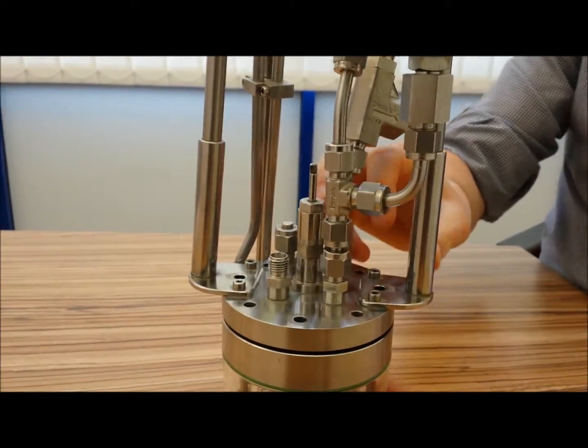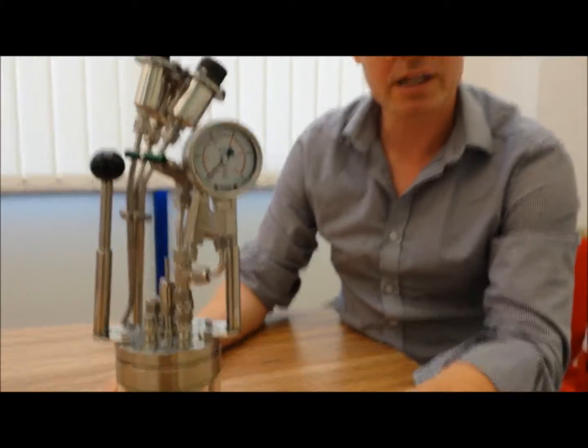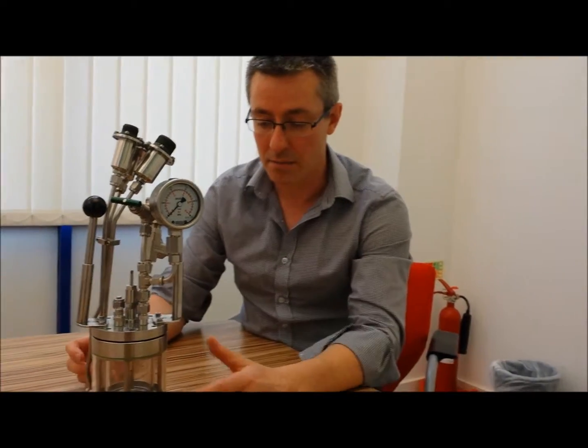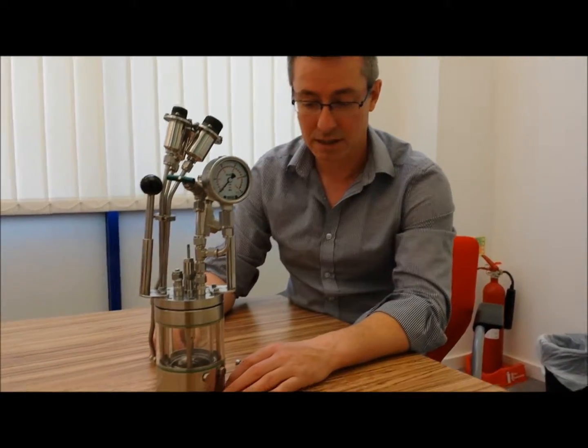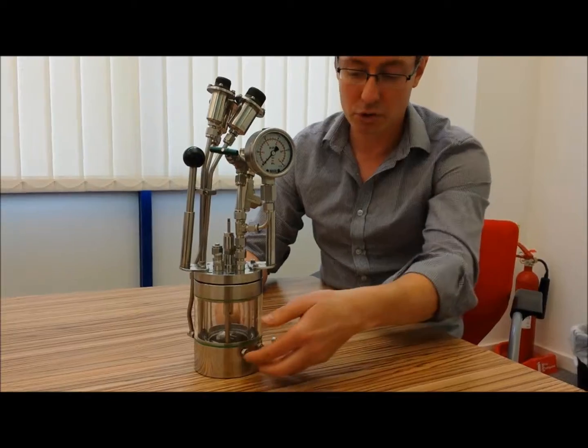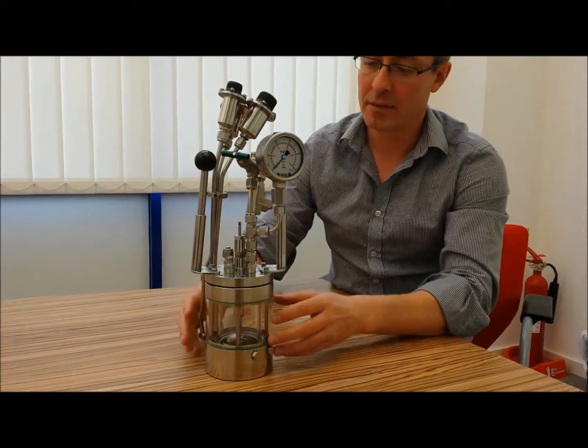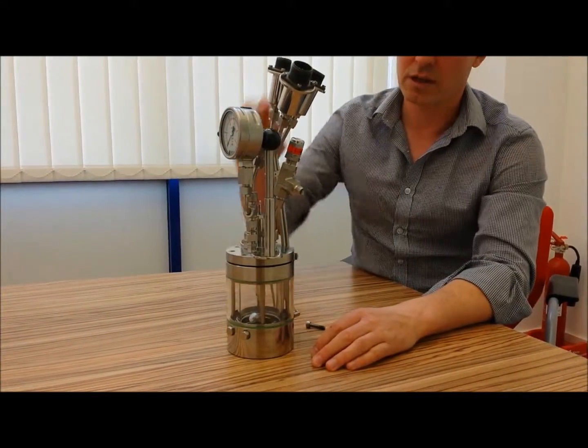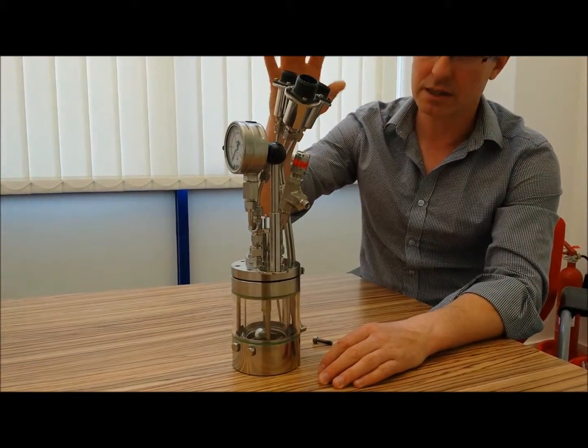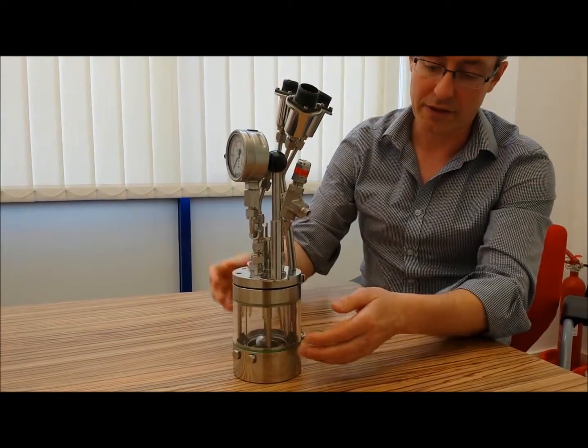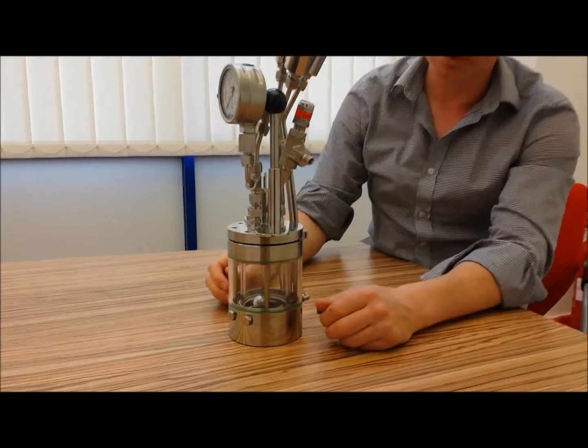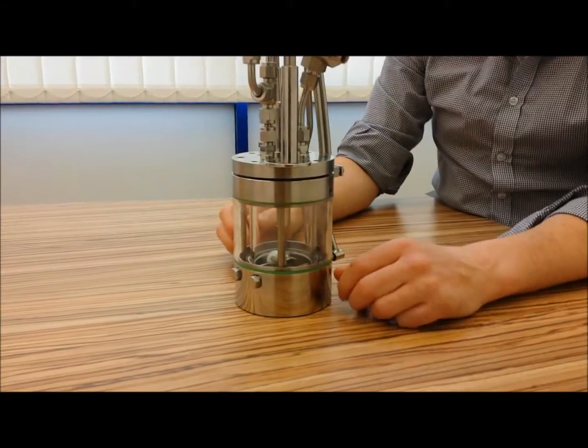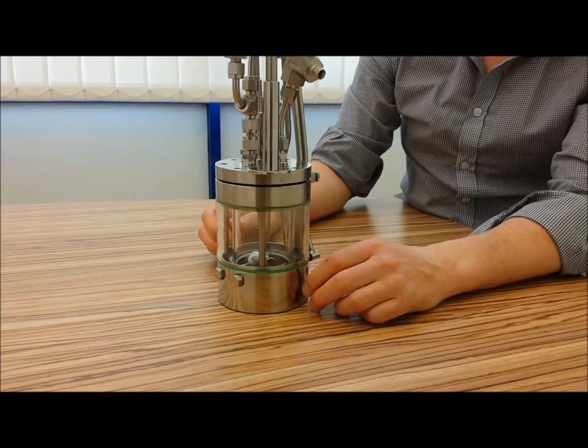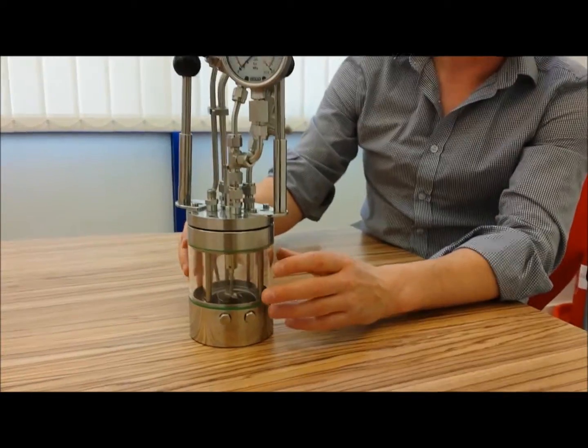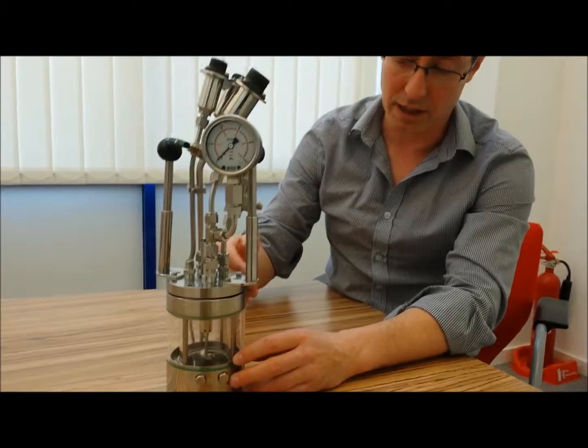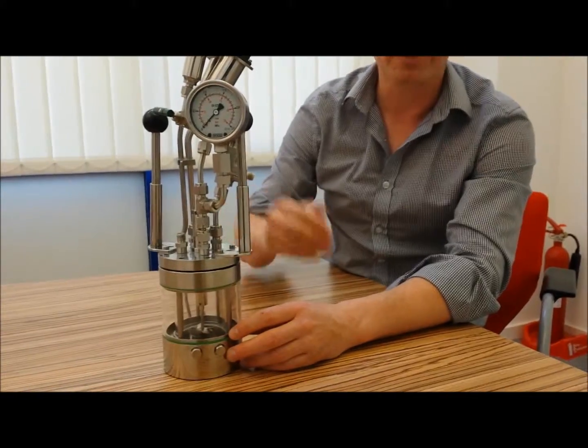And let me summarize what we've said. Here's a 250 mil reactor, minimum working volume about 10 mils, with 4 ports on the top, 2 ports on the bottom. The 3 electrical connections are for a validation heater, which you really don't need, the internal reaction temperature, and then there's a special transducer in the base of this calorimeter where there's a Peltier and a whole series of temperature probes. Just to say that the vessel is double walled, so we have a glass wall, an air gap, and another glass wall.